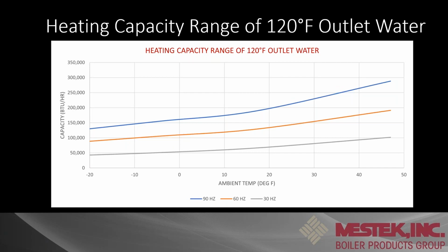As I move into this one, it's the same type of chart, but now we're showing it at 120 degree water outlet. What is the difference here? Our capacities drop off because now we're putting out hotter water and the compressors are working harder, but not a ton here at 120. At minus 20 degrees, at low speed, 30 hertz, we're somewhere around 50,000 BTUs, a little bit lower. At high speed, 90 hertz, we're a little below that 150,000 BTUs at minus 20. And looking at 40 degrees again, upwards of, let's call it, 260,000 BTUs at high speed and close to 100,000 BTUs at low speed.